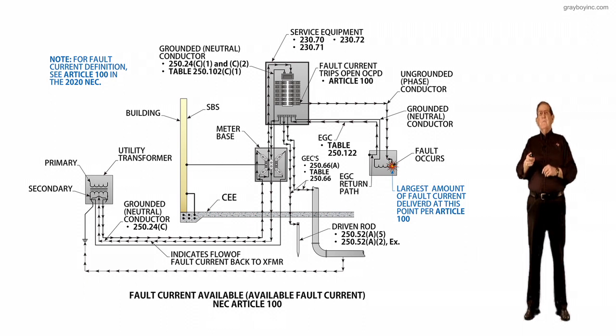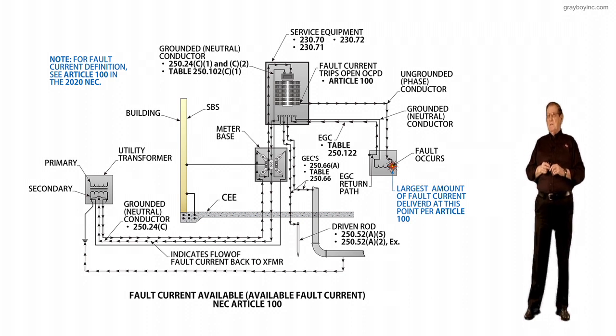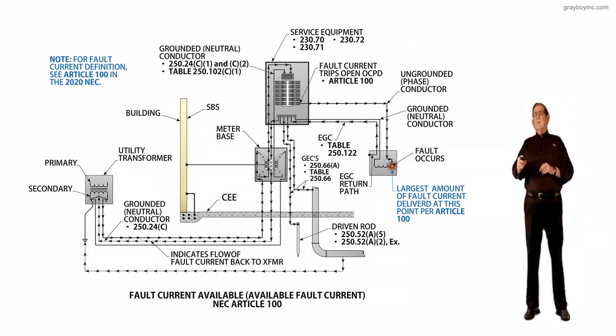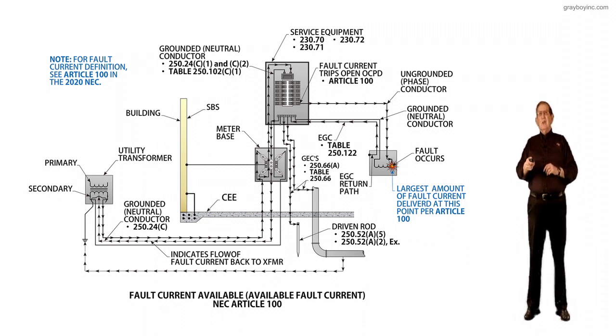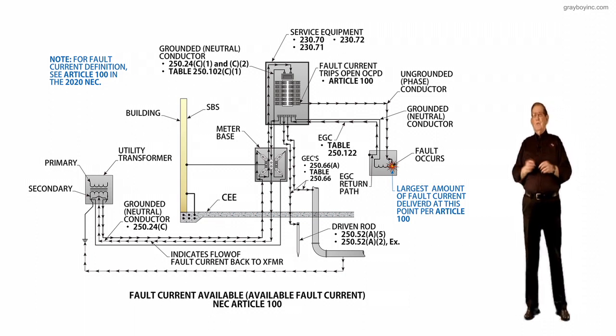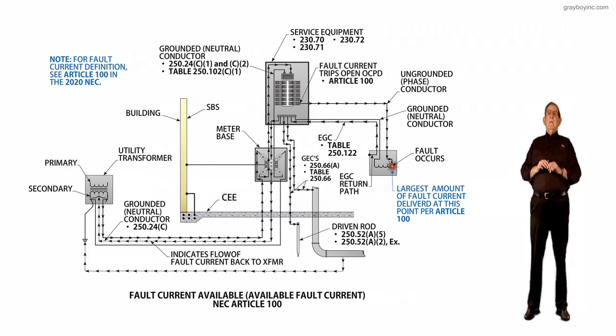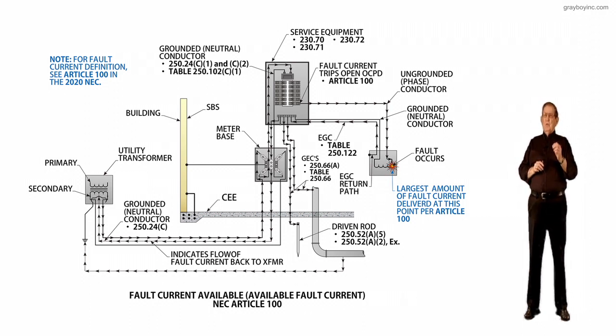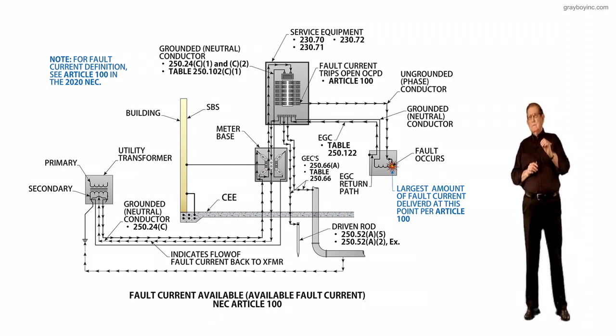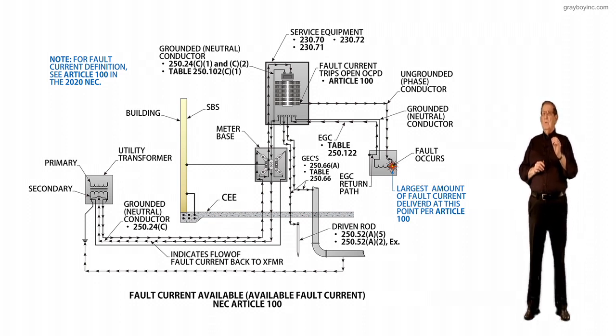And we just said, for example, if you had a 200 amp overcurrent device here, then I believe table 250.122 would require a number 6 equipment ground if used. Now, the grounded conductor that's routed from the grounded bar in the panelboard back to the transformer. We don't have an overcurrent device ahead of that transformer. So we would review the size of the conductors and say they were number 4 terminating to, say, a 225 amp main. Now, we'll just give an example here. Then the number 4, from table 250.102(C)(1), would have to be at least a number 2.